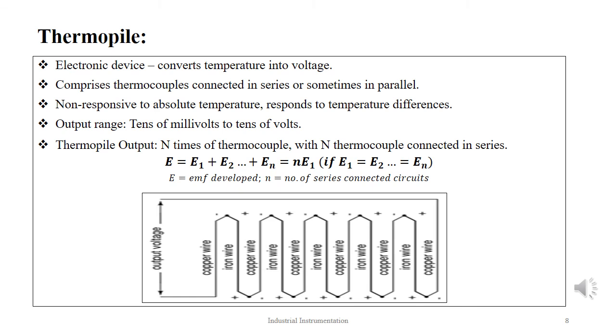A thermopile is an electronic device that converts thermal energy into electrical energy. It is made up of several thermocouples connected in series or sometimes in parallel connection. The thermopile does not respond to absolute temperature but generates an output voltage that is proportional to the local temperature difference or temperature gradient. The thermopile output is in voltage and ranges from tens of millivolts to tens of volts. The output voltage of a thermopile is n times the response of a single thermocouple if n thermocouples are connected in series configuration. The resultant thermopile voltage output is given as shown in the equation below, that is E equal to E1 plus E2 plus dot dot dot to En.